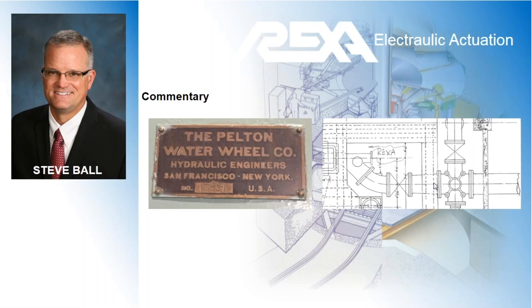However, I think due to a misconception from the person operating the load bank, we went from half a megawatt all the way to 3.5 megawatts in one shot, and we were completely unprepared for that. However, right then and there, it took just over 1 second for the turbine to regain control and recover frequency. That was a huge load increase, and that was one of our last test steps, but we ended up doing it right off the bat. The actuator did exactly what it was supposed to do. It opened up the needle at the 3 second per inch rate, and the recovery was just over a second, which was within our criteria of getting a stable frequency within 2 seconds of system disturbance. That actually worked out very, very well.